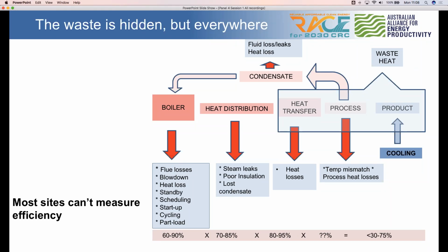Firstly, for most processes there isn't a good understanding of even what temperature is required to do the process. Then there's the actual activity of centralised process heating with reticulated steam and condensate. Most sites have no idea what their thermal efficiency is—they can't measure it, many don't even measure the fuel in, and no one has a good idea of how much heat actually goes to the process.